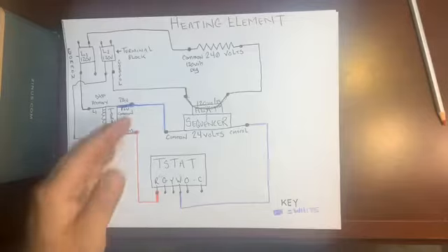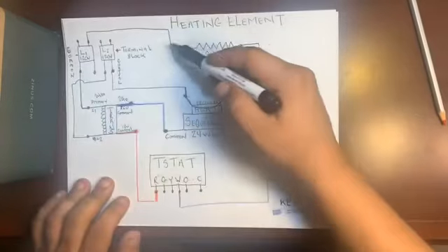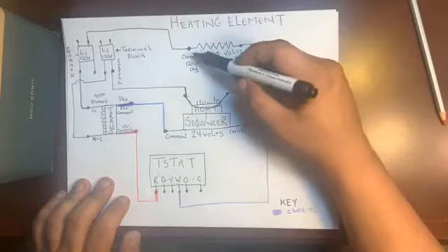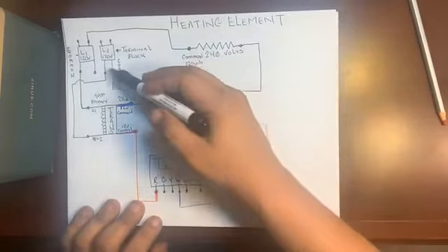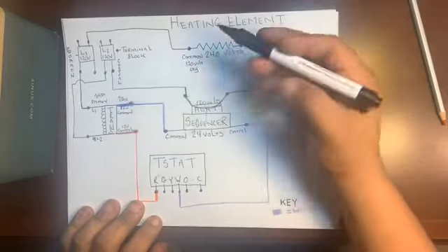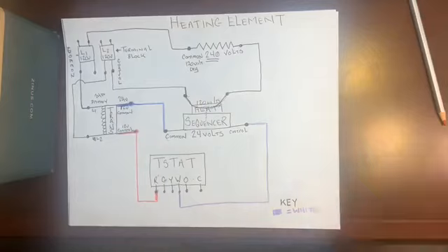Now that you understand common and control, a constant common to the heating element, if it has 120 volts, the heating element will not turn on. It's only when it receives the other 120 volts and receives a complete 240 that the heating element turns on and heats the home. So imagine this.